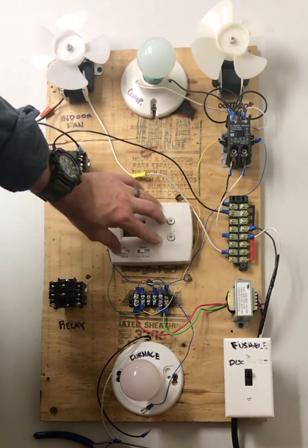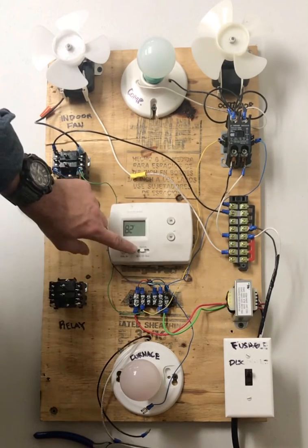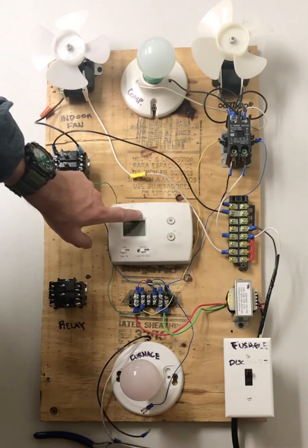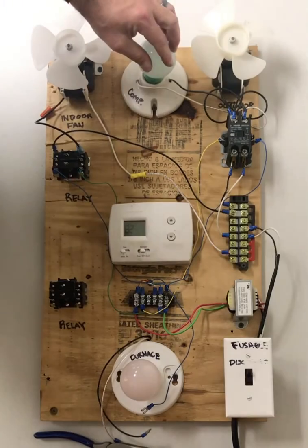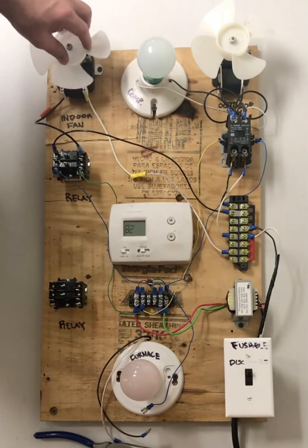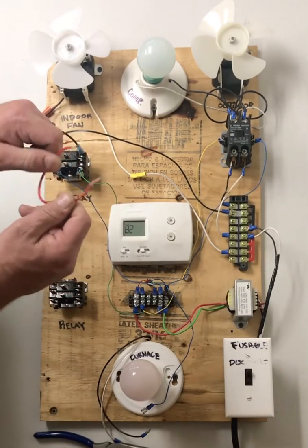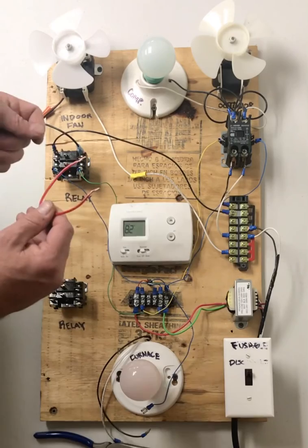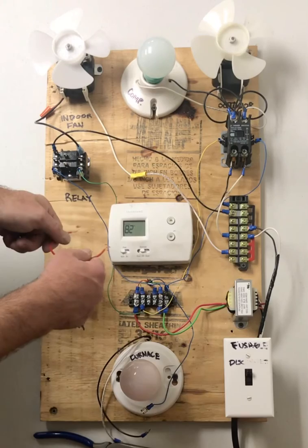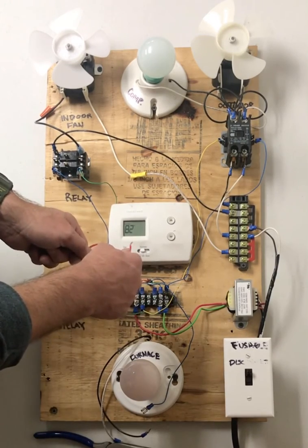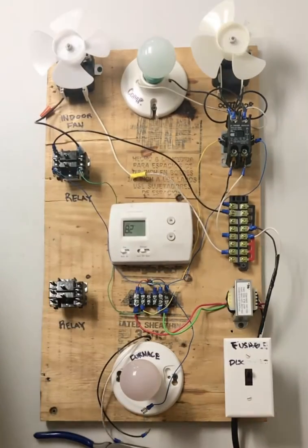Now the thermostat has the ability to take the power from R and send it to wherever it needs to be. So if you're making a cooling call, it'll send it to Y and to G, because it knows when you make a cooling call, it needs your condenser, your compressor, and your indoor fan running all at the same time. But when we're jumpering it, we only have one jumper. So unless you make some sort of jumper that's got an extra lead on it where you can test them all at the same time, you can only test them individually. Which is why I tested from R to G to make sure the fan was working, and then from R to Y to make sure that the compressor and the outdoor condenser was working.